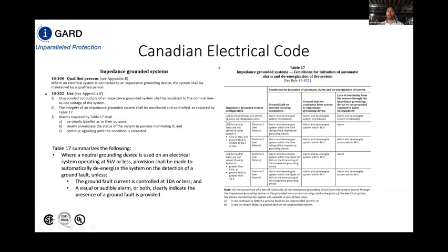And in addition to that, I did skip over this first row. It's because I mentioned to you at the beginning that we should not be distributing the neutral in a resistance grounded system, simply because on each of these conditions, we have to alarm and de-energize the system immediately. So really, resistance grounding doesn't provide a benefit when you have a 3-phase 4-wire system.